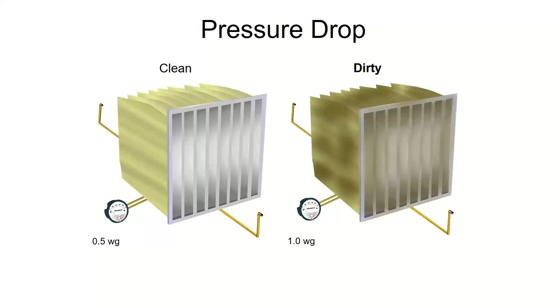At a commercial building with a little rooftop or a furnace, they probably don't do that either. A big building with large air handlers, like campuses, hospitals, universities, VAV systems at a school, those folks typically would. They would have a pressure sensor across the filter telling them when to change the filter. Now, whether that pressure sensor is set up correctly, that's a whole other discussion, but they probably have it there. There's lots of ways you can measure those pressure drops in the field with different tools, manometers, and so forth.